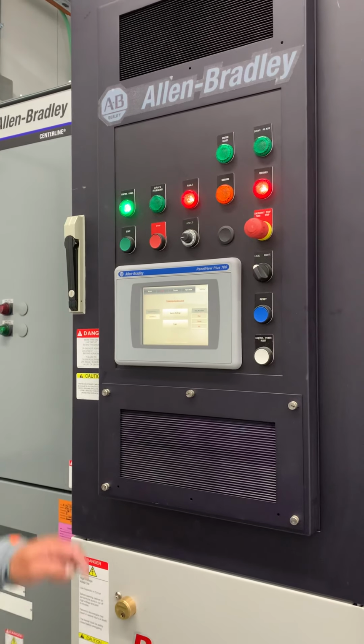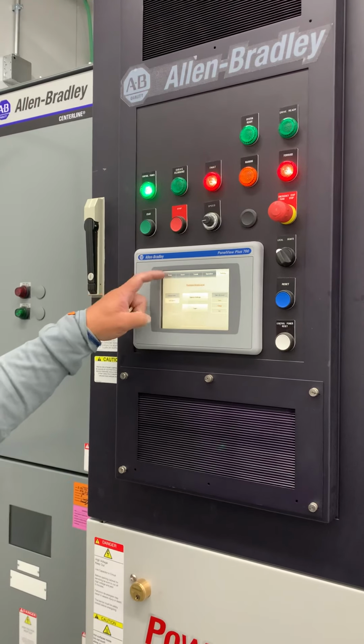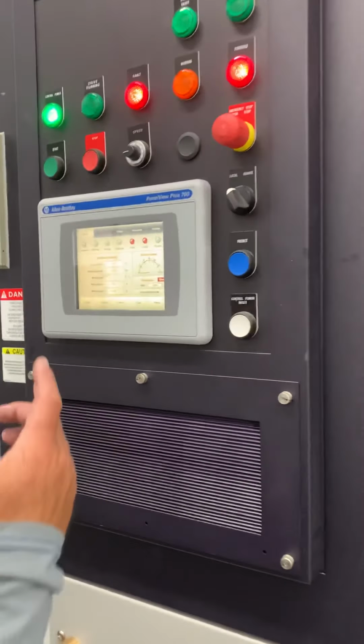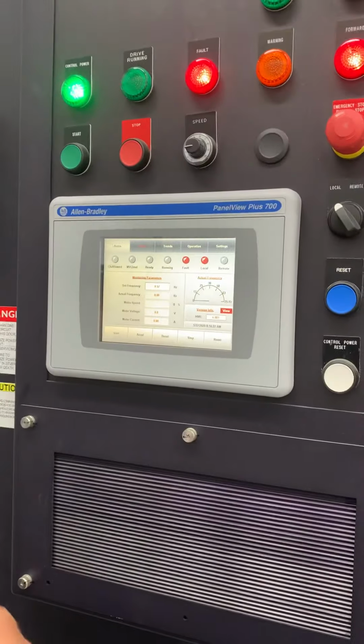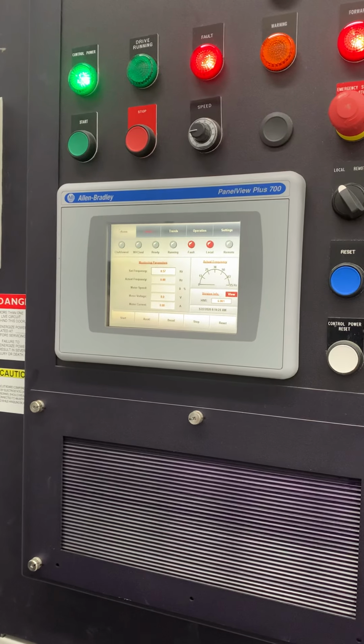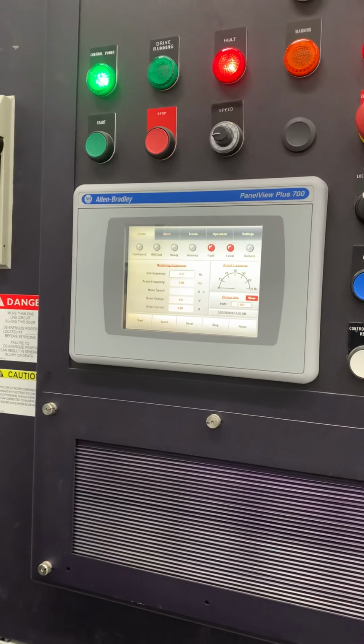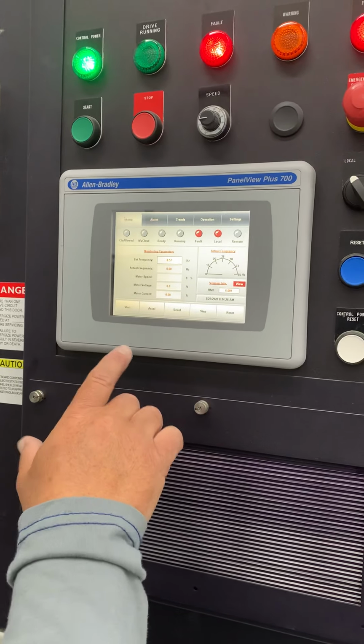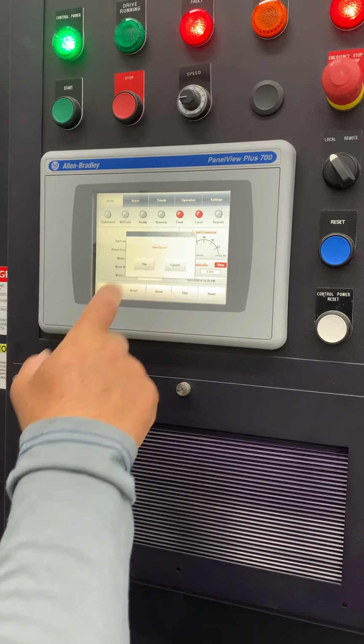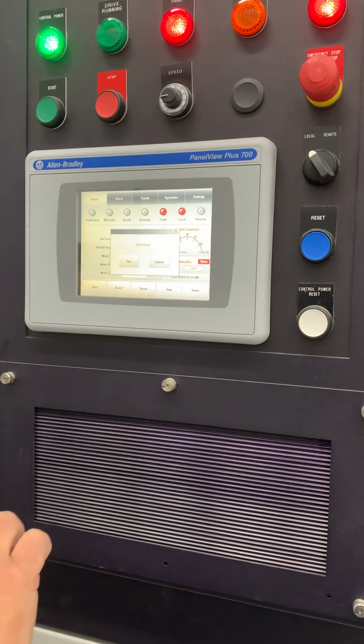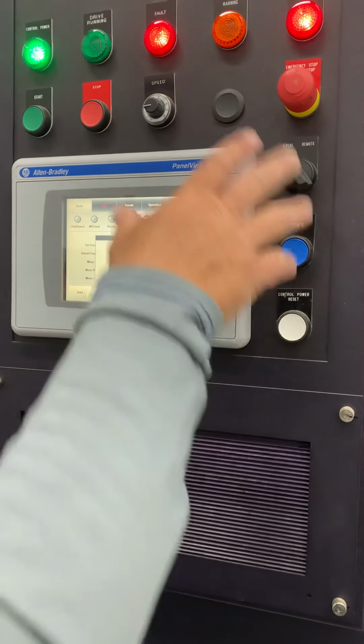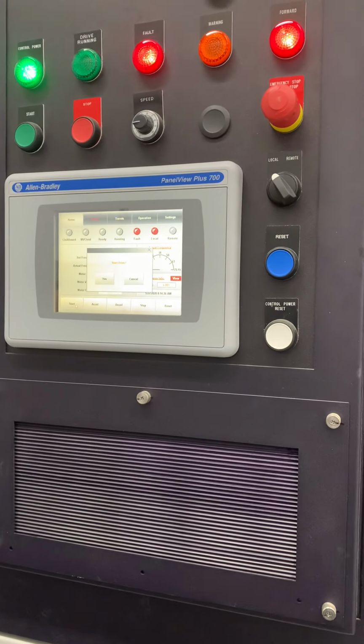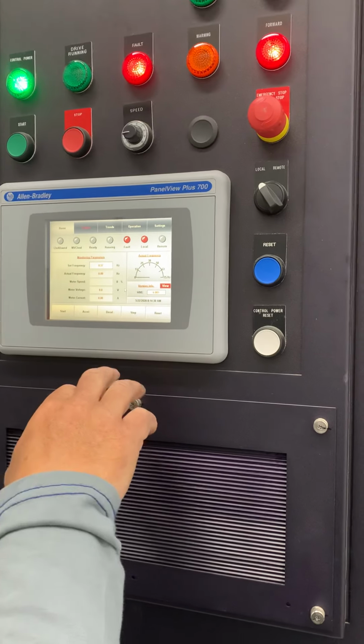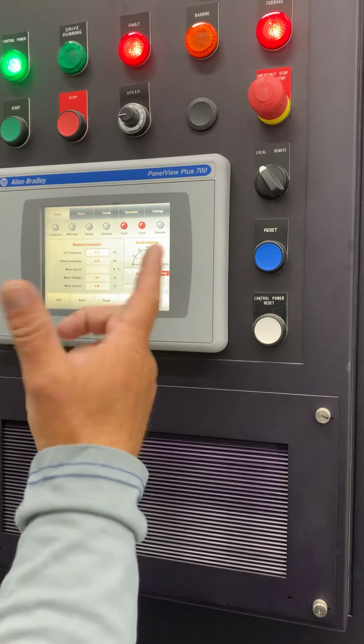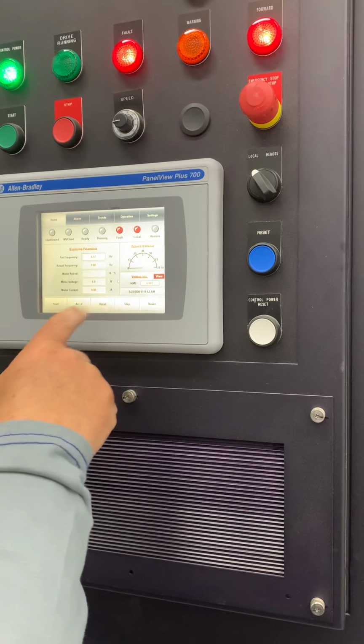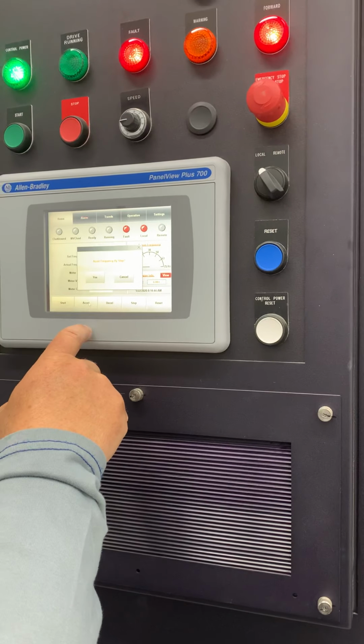Okay, very well. But really, it's pretty simple. I mean, you've got your home screen, so that tells you your hertz and your motor speed, your voltage, current, and all that. So you can also start this from the touch screen if you really wanted to. That's what we do if we don't have the local controls. We use the touch screen. So start, stop, that's a reset just like that. Accel and decel. Where you set the times?